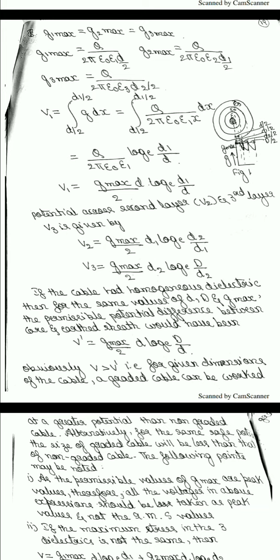Okay, this is the capacitance grading. Obviously, if V is greater than V dash for given dimensions of the cable, a graded cable can be worked at a greater potential than a non-graded cable. Graded cable means the stress will be uniformly distributed, so a graded cable can be worked at a greater potential than a non-graded cable. Alternatively, for the same safe potential, the size of the graded cable will be less than that of the non-graded cable, because the stress on the cable will be equally distributed.